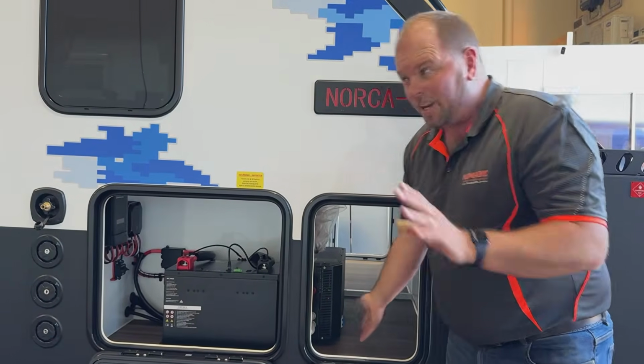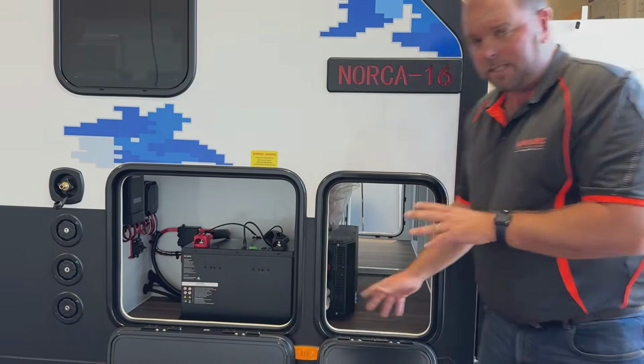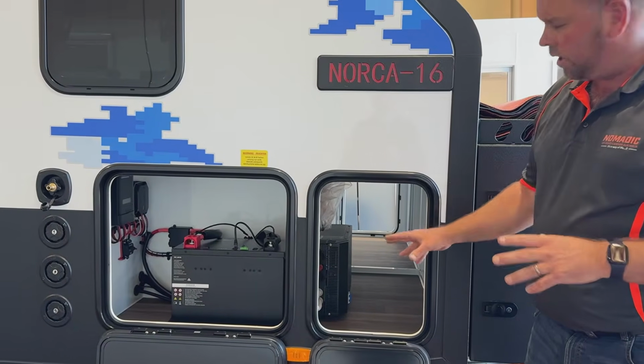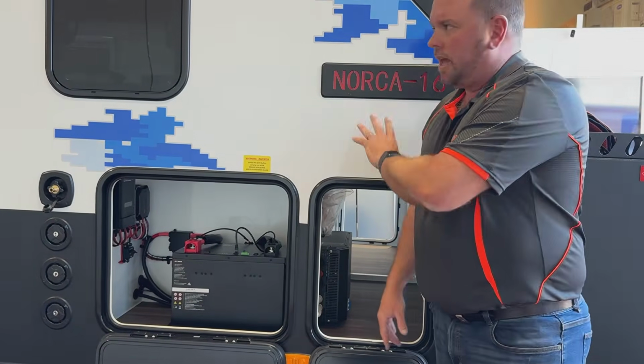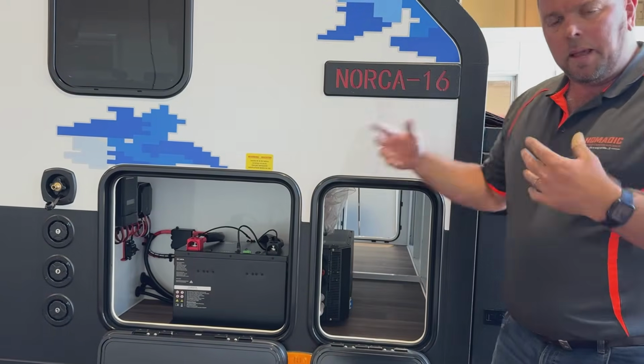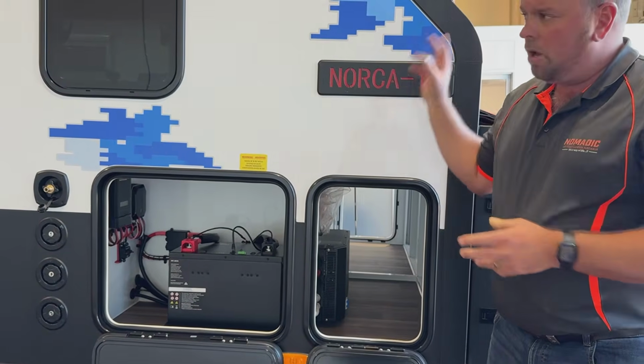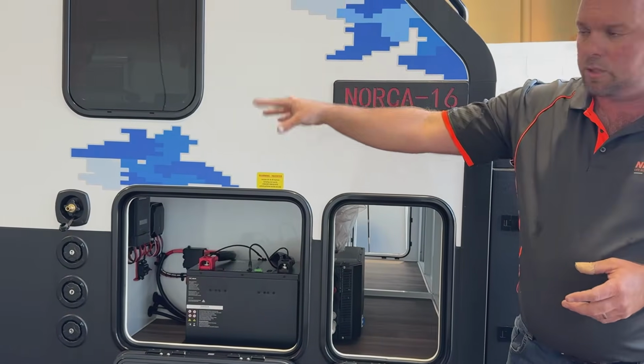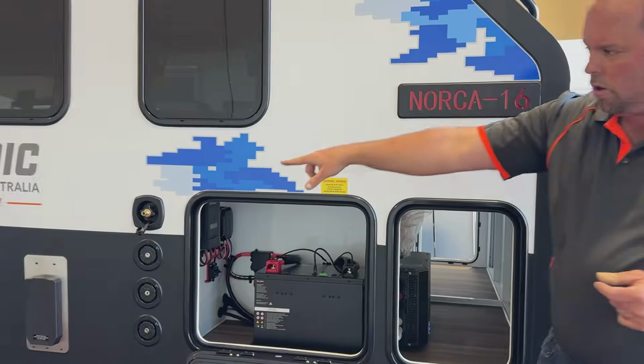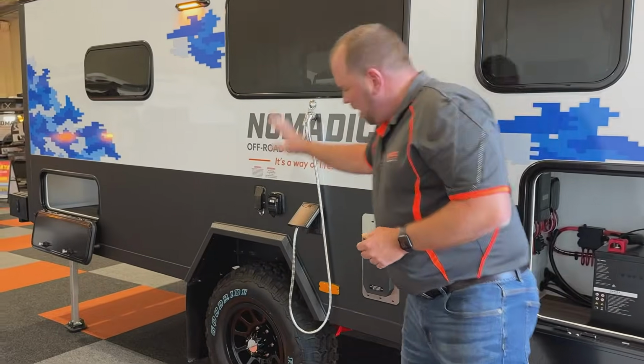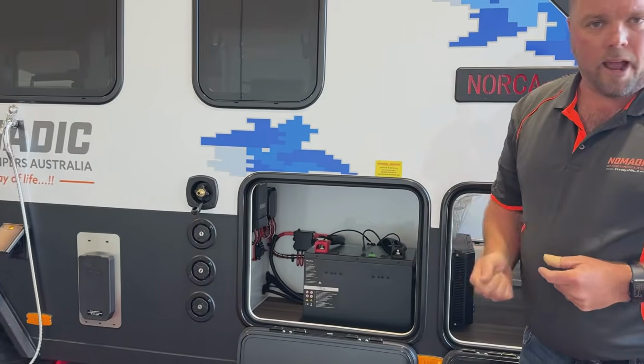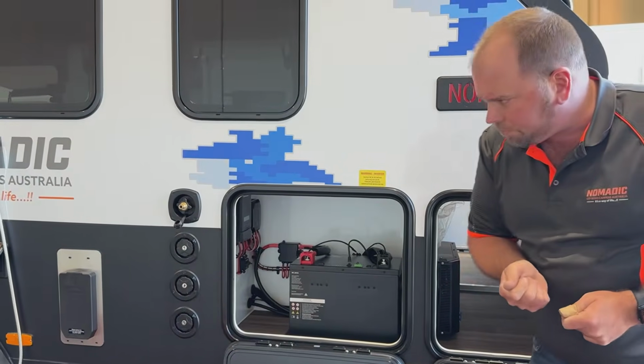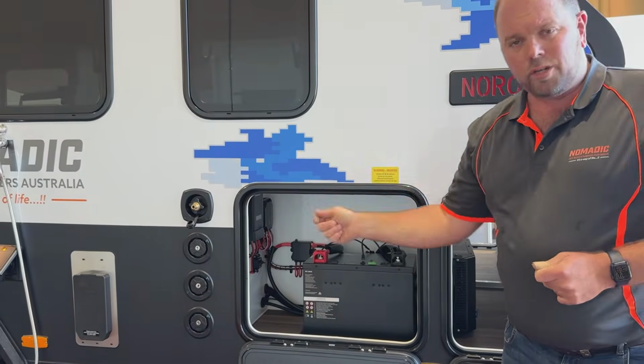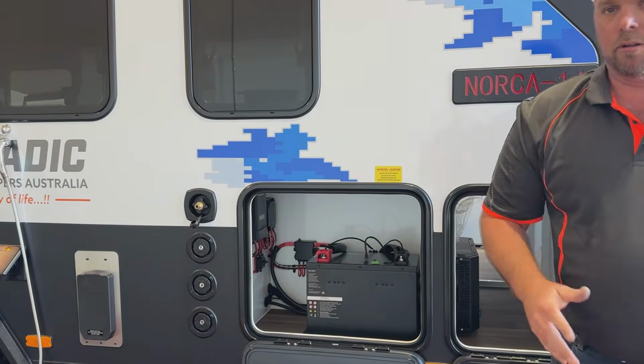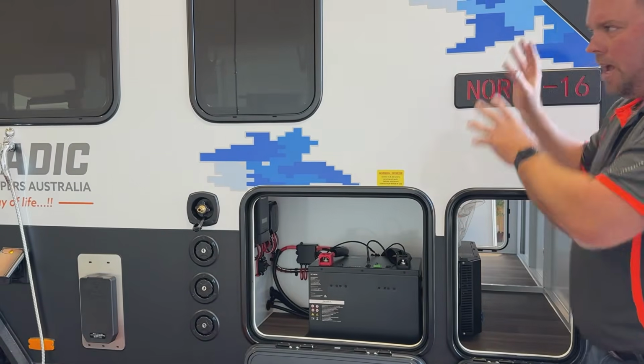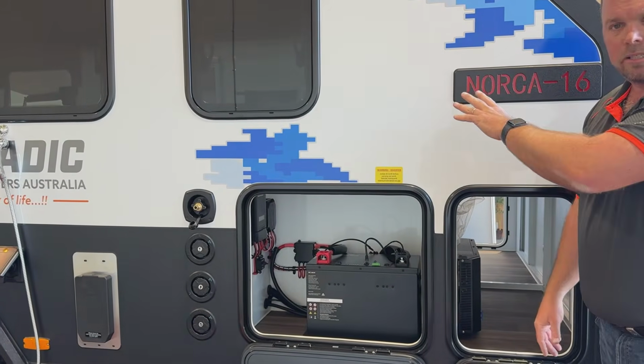Importantly, and not all caravans have this, our inverters have an RCD, so they've got a built-in electrical safety switch. If you plug in an appliance on the caravan and this RCD trips, it means you've got an issue with the appliance on the caravan. We also have another RCD, or safety switch, underneath the seat, which controls our 240 volt input. If you are plugging in at an old caravan park or a generator and it trips the switch, it means you've got an issue from the external of the caravan. If we plug in and it trips the switch down here, it means the appliance is faulty.